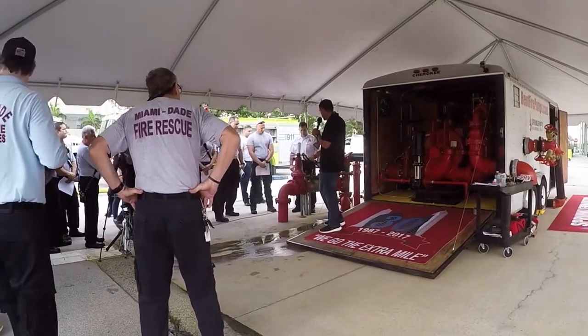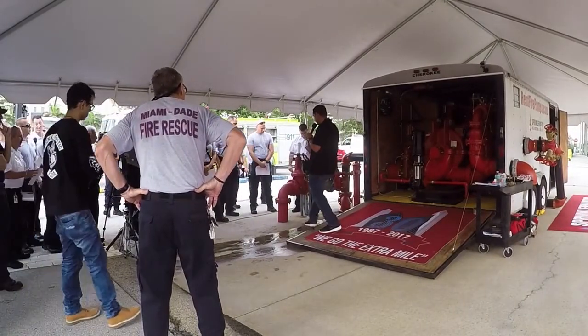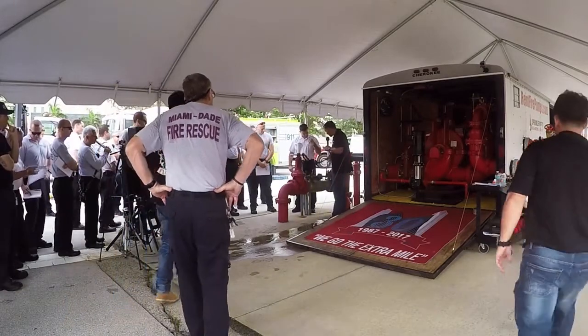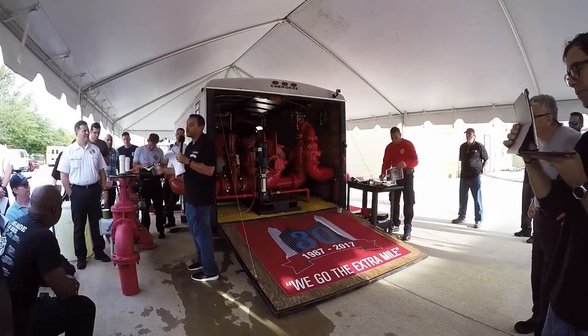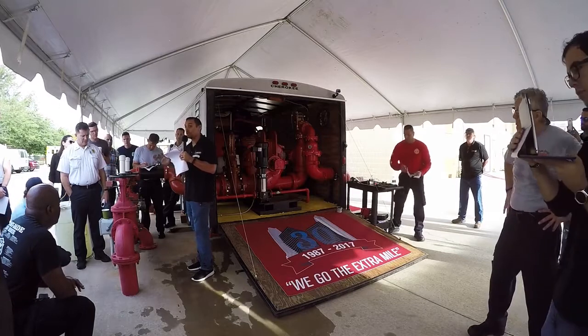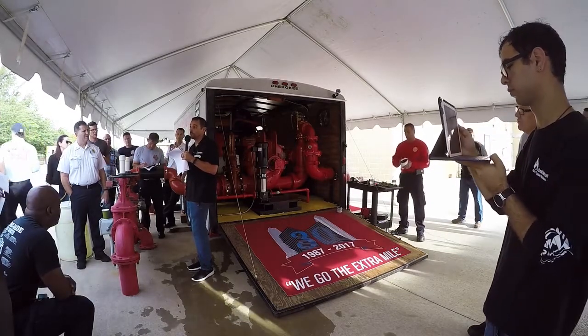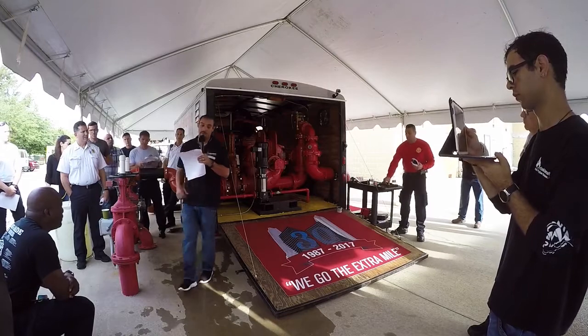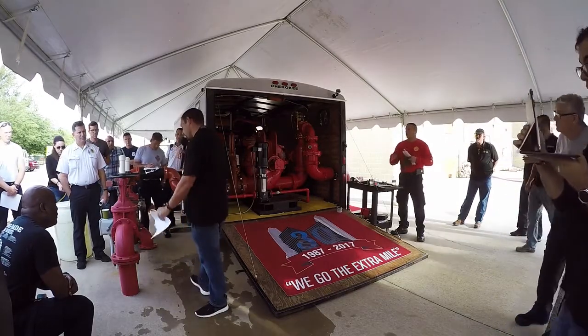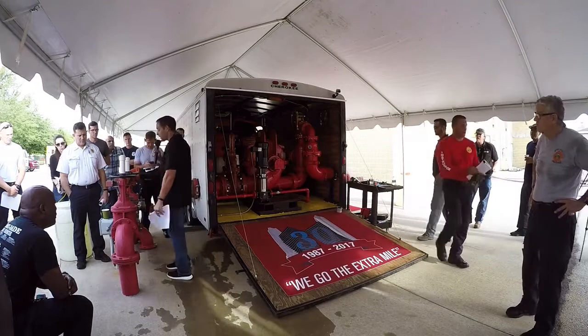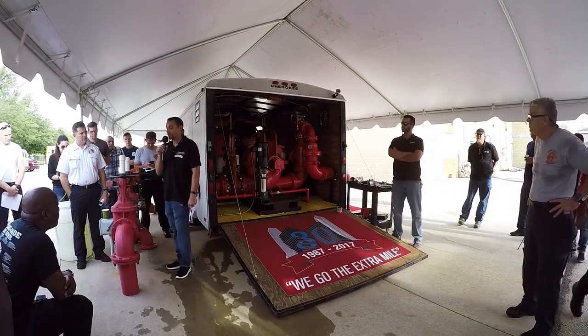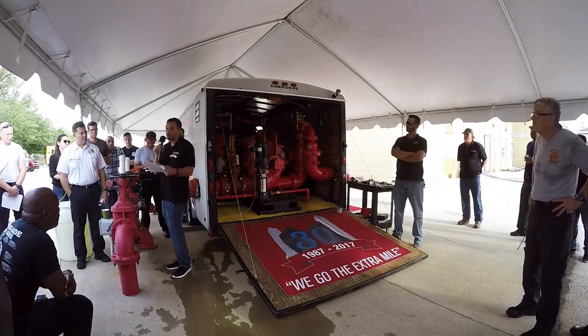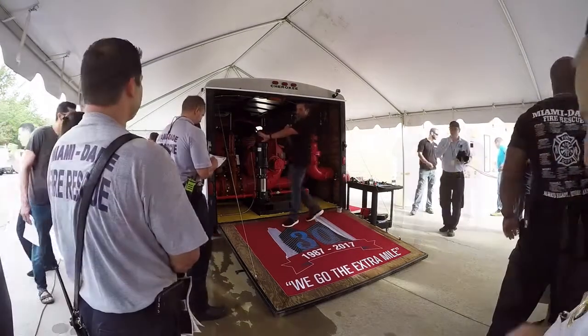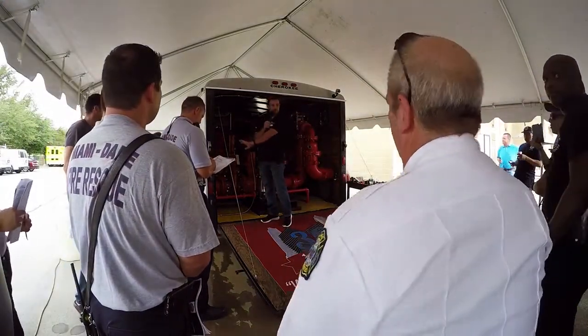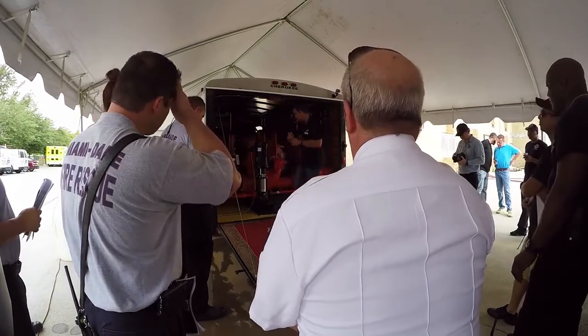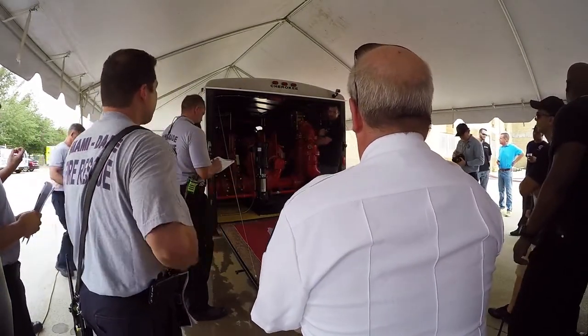There's two double check valves in it, the big one where the water flows, and then there's a metered side. Through the backflow, we either go directly into a riser system, or in this case, we go directly to our fire pump, okay? And what a fire pump does is take the pressure of the city water and add to it, okay? So what it adds is volume and pressure, okay? Everything on the backflow side would be city pressure. Everything on the discharge side of the fire pump is under pressure.